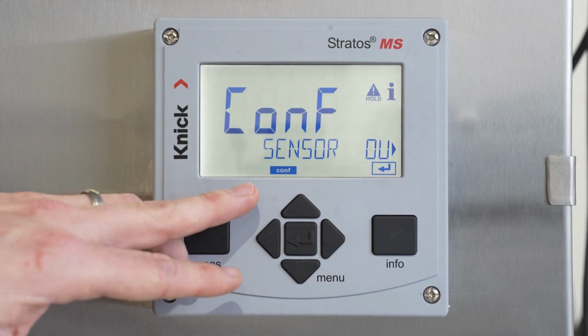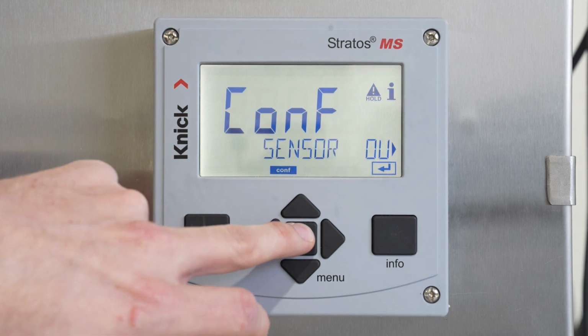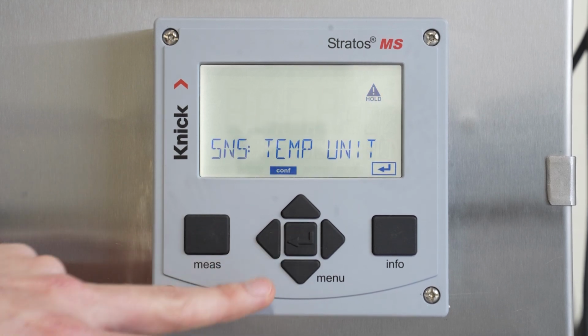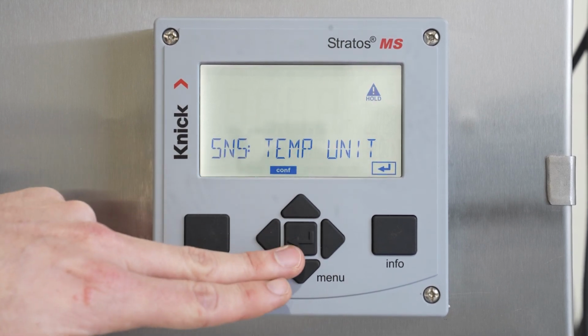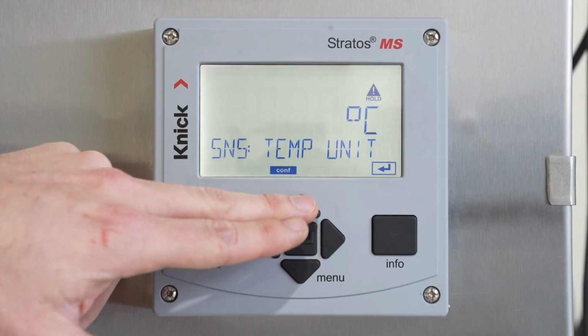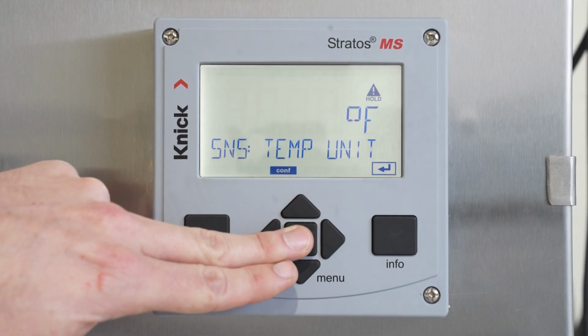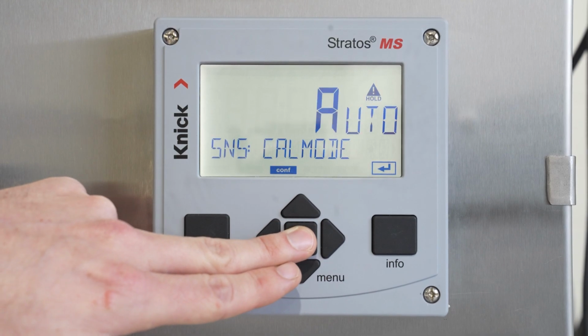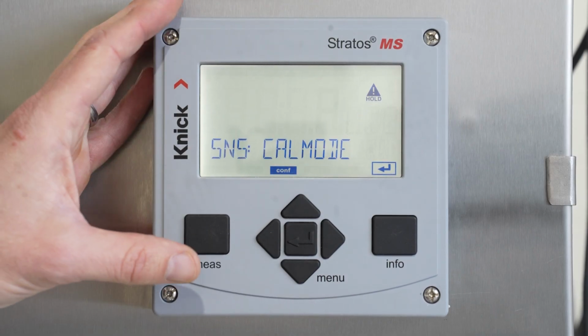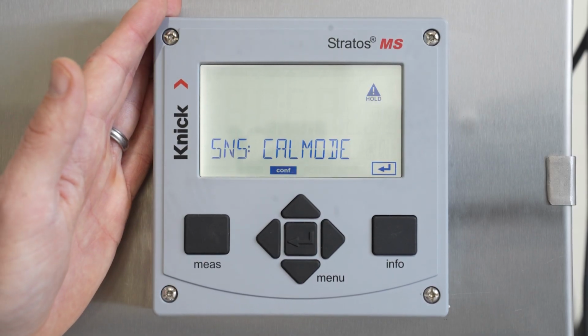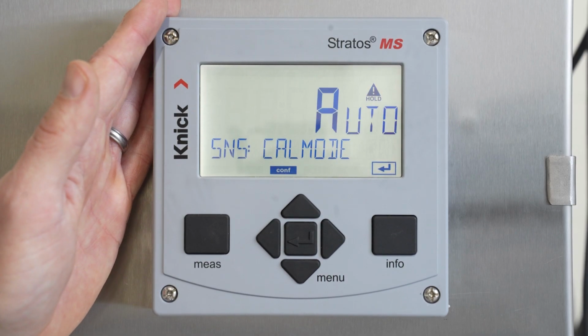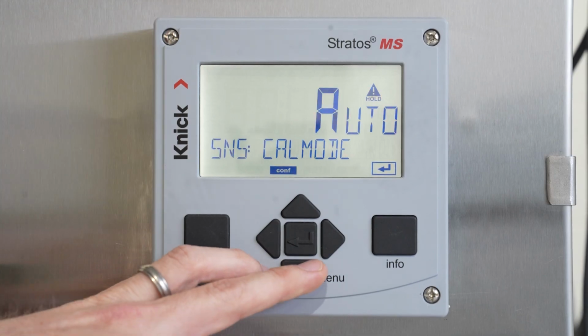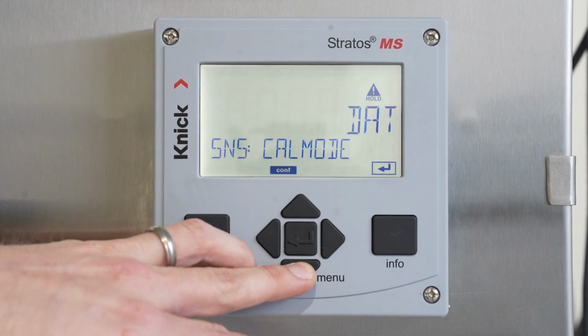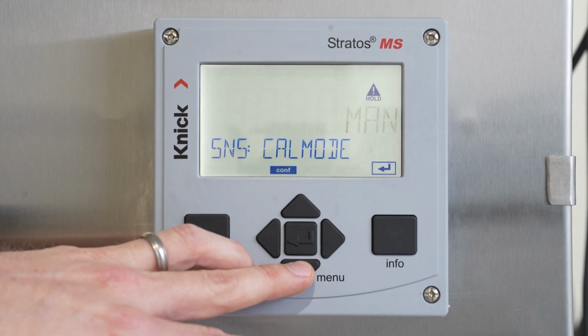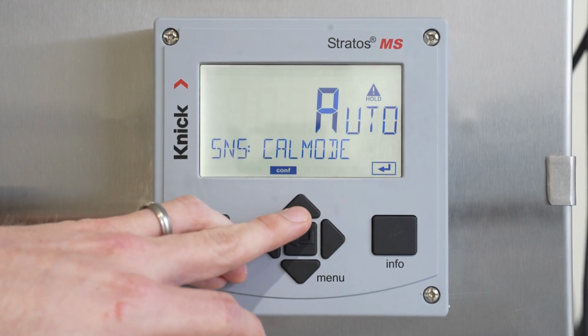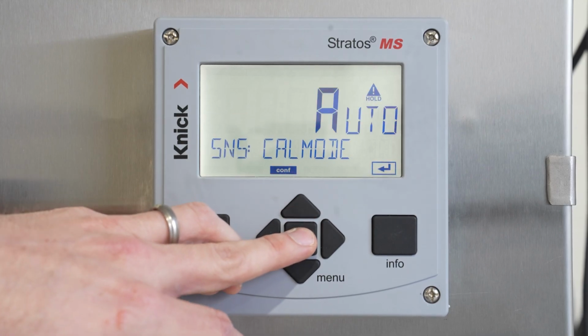Here, we will set up our sensor. We will press enter on sensor, and it prompts us to select our unit for temperature measurement. We will select degrees Fahrenheit and press enter. Next is our default calibration mode. The Stratos MS allows for automatic calibration, manual calibration, or data entry. We will select automatic calibration for this setup.